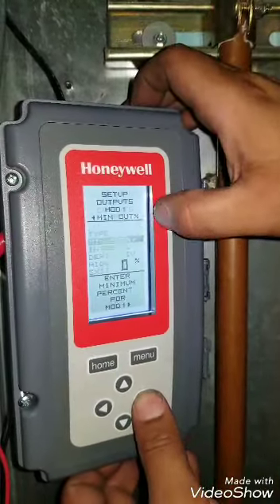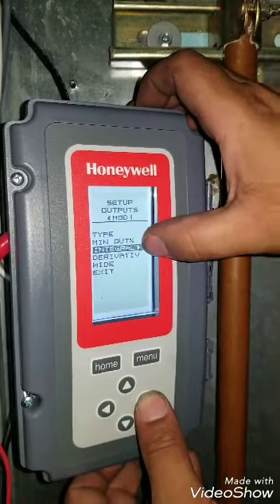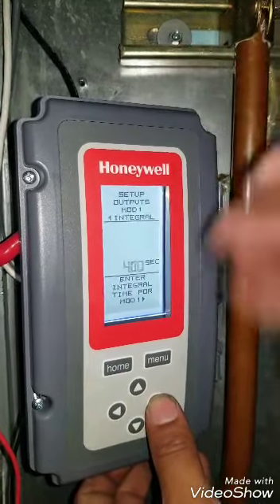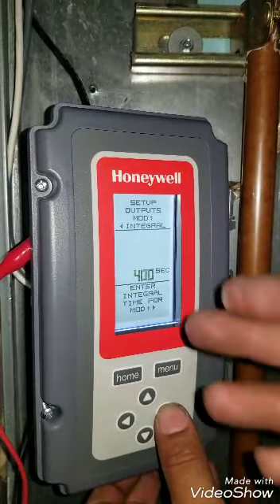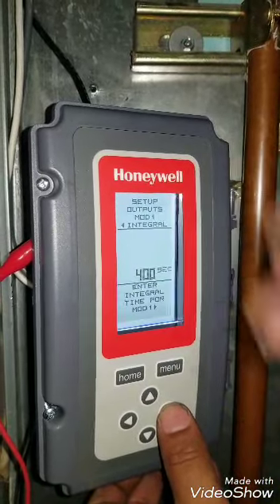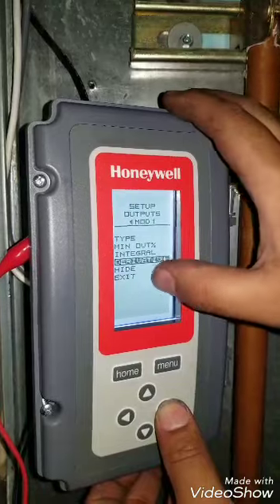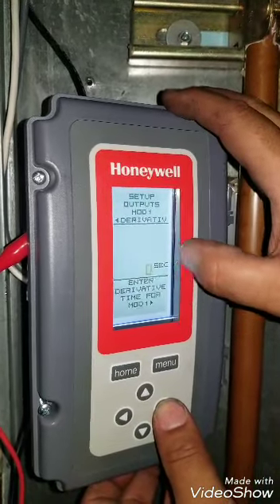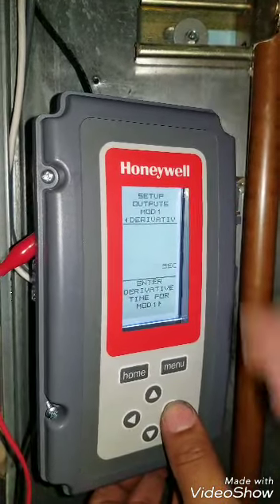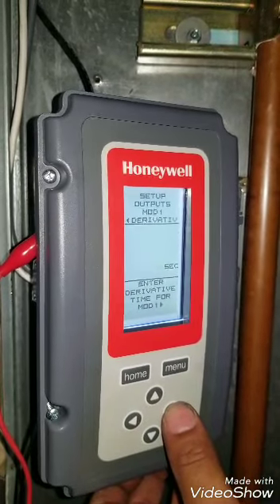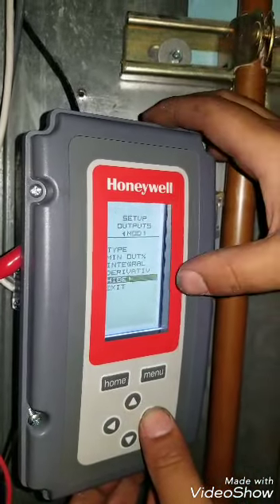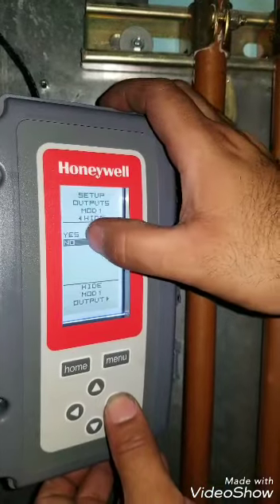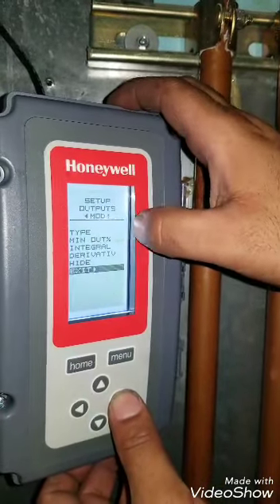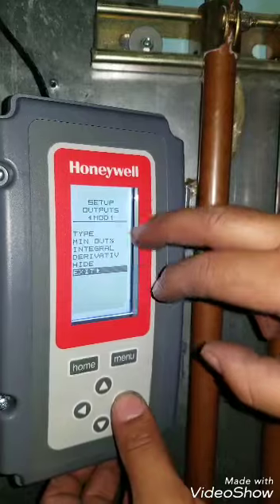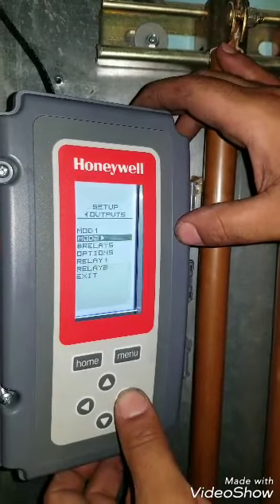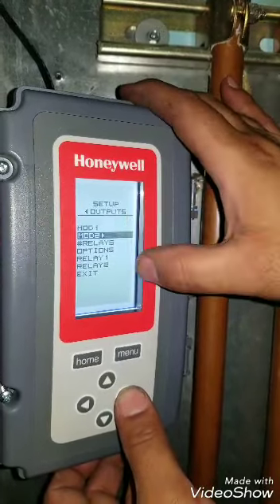The minimum output percentage, you could leave that at 0. Integral, 400 seconds. You could play with that later on. What that means is that it's going to take 400 seconds for it to modulate up and down. The derivative, you can leave that at 0. If you got to play with it, you can put it at 30, 60, or 90. That's also intervals. Hide, nothing. You never want to hide it. You always want to leave it no. Okay, hide means that it'll hide the setting that's on the screen. You don't want that. And then that's it. That's pretty much the setup.